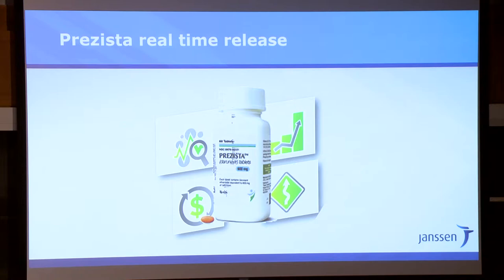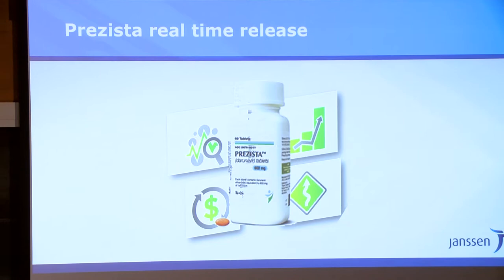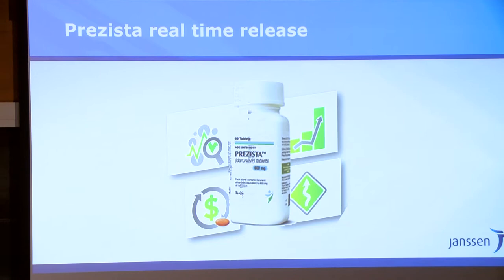Another very important part of our goals is the idea of real-time release. If I have my sensors, my models, my data analytics, I should be able to know instantly that a batch is ready to be released. We've been working with Rutgers. We were one of the very first people to get a continuous tableting line approved by the FDA, and now it's been approved in 10 other countries as well. On top of that, we've now gone back and did real-time release — given the parametric data, given the PAT data, we were able to submit and get approved a predictive model, especially for dissolution.